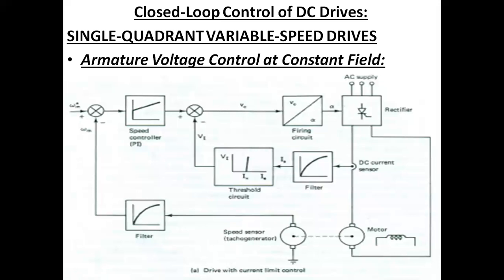While using proportional integral in a closed loop control system, PD, meaning proportional and differential, and PID, meaning proportional, integral and differential controllers, are also often used. But out of these, only PI is more useful, and the others are not preferred in converter drives because of the presence of substantial noise and ripple in the current and speed feedback signals.